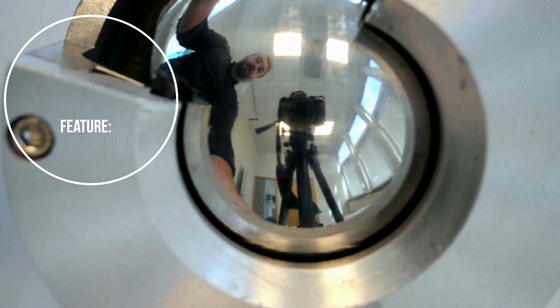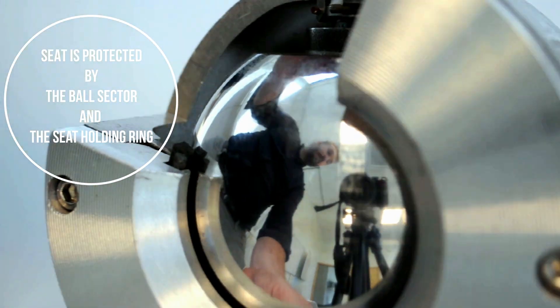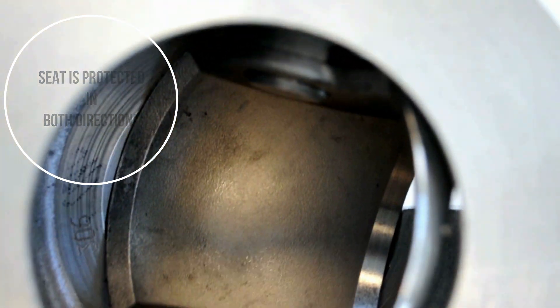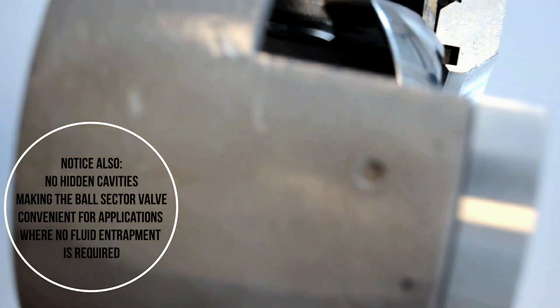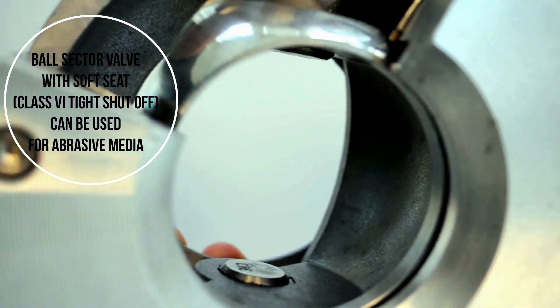Another feature is that the seat is always protected when the valve is fully open or fully closed. You can see here that the seat is completely protected by the ball sector and the seat holding ring — both front and back. Here the seat is completely protected when fully closed, and when the valve is fully open, the seat is also protected by the ball sector and the seat holding ring, front and back. This means that the valve can be used with a PTFE seat or soft seat, even for abrasive media.